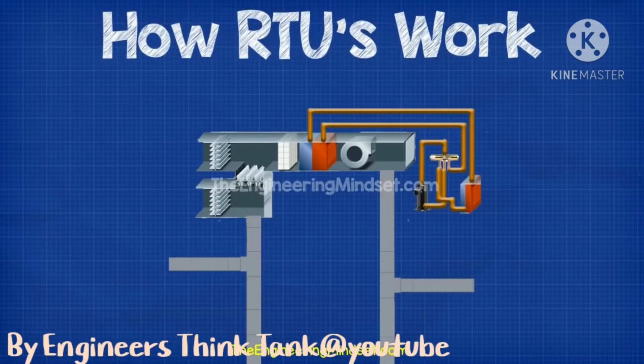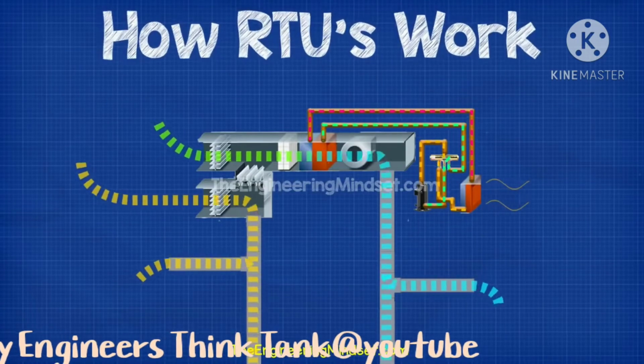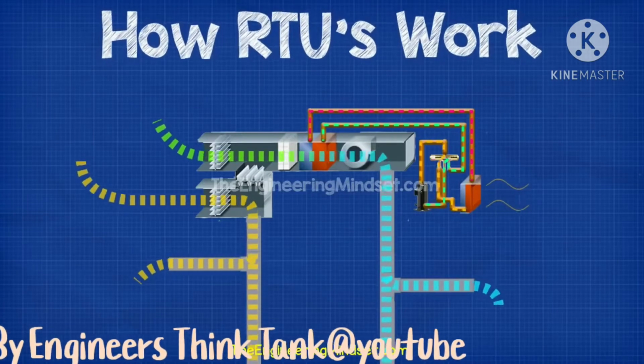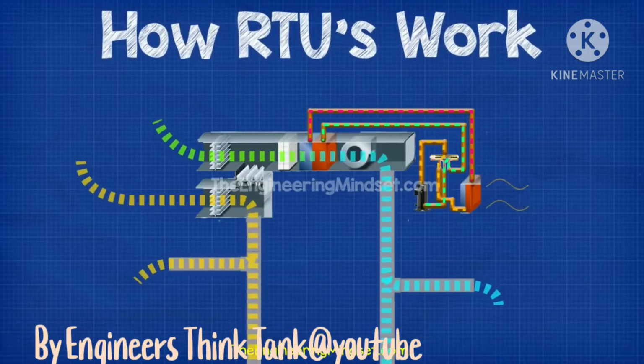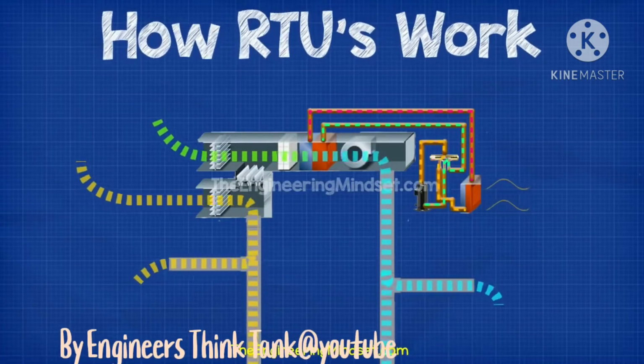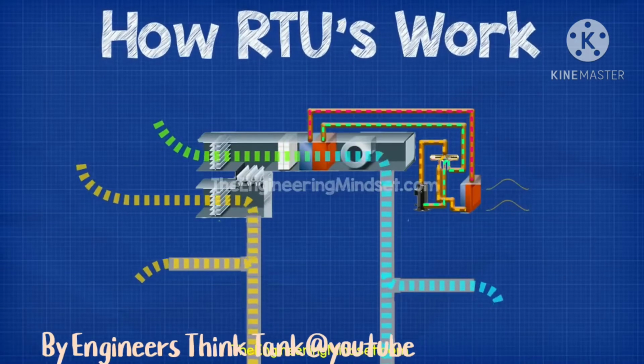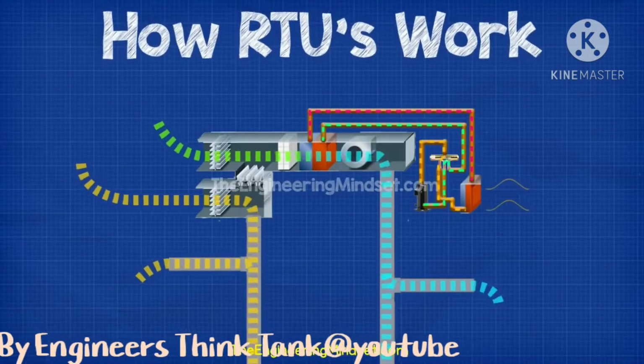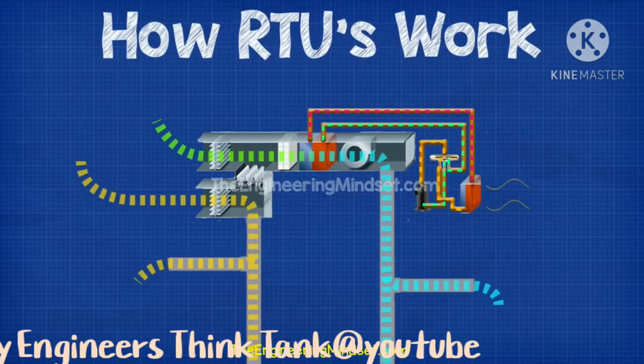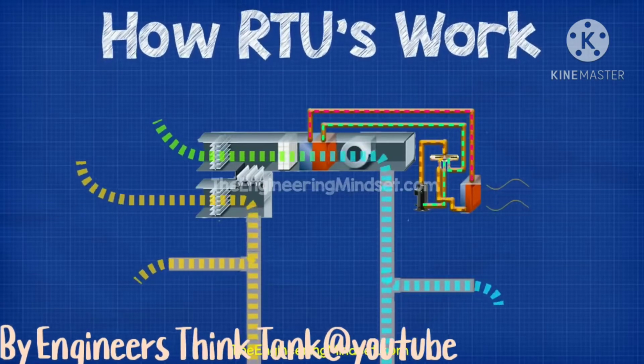This contains a number of dampers to control the flow of air and can allow air recirculation if conditions are right. The unit will also contain filters to clean the air, as well as heating and cooling coils and at least one central fan. The refrigeration system is also connected to the back or the side of the unit, and this is used to control the temperature.